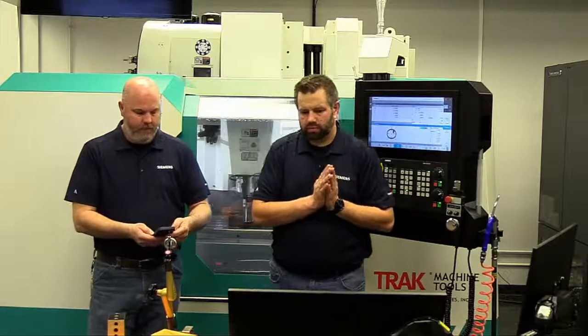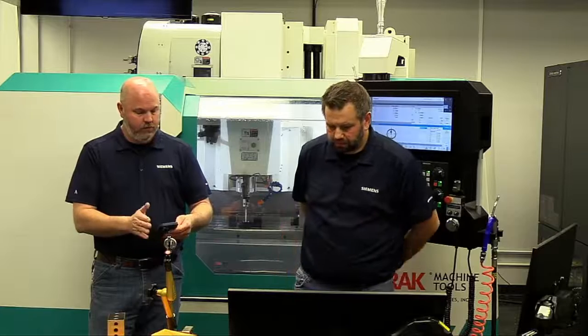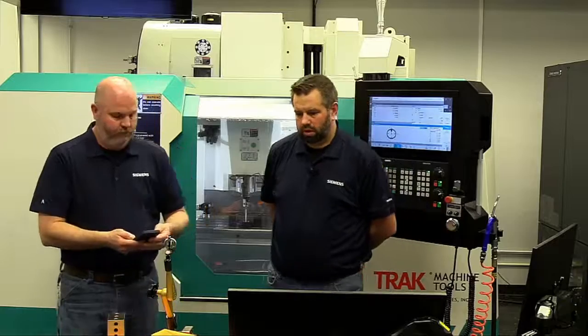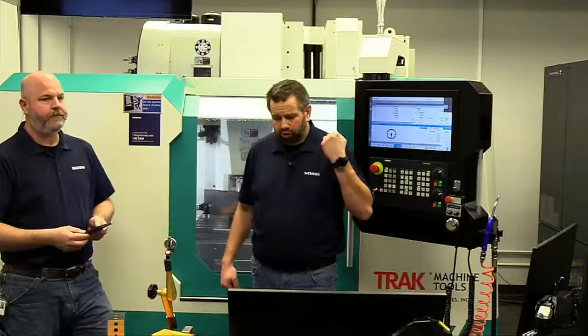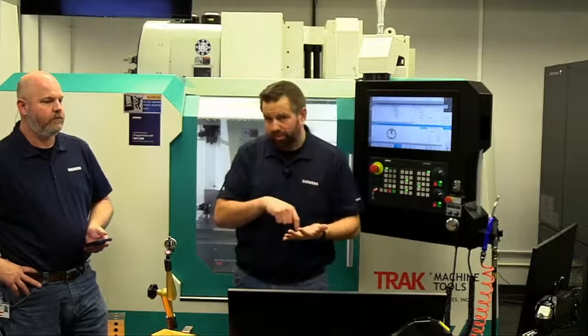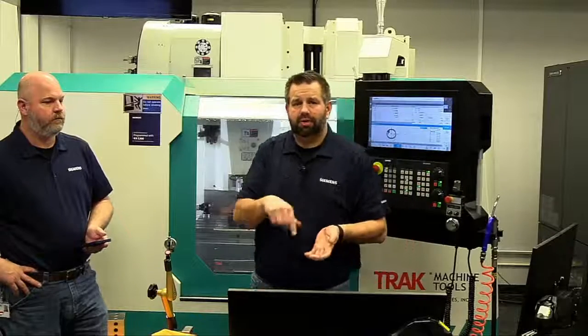Let's see what else we got here. This is an interesting one. I have a machine where every time I measure, the X and Y moves just a little bit, kind of jumps on me before it actually takes the measurement. Any idea what's causing that? There are two types of commissioning probes for our control. One is what we did today. We didn't find the center of the ring, we just eyeballed it and it went around twice. The first time it found the center of the ring, and the second time it calibrated the stylus, finding the measurement from the center of that radius to the edge of that hit.